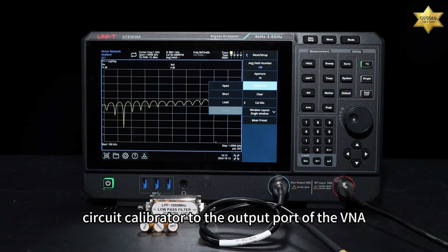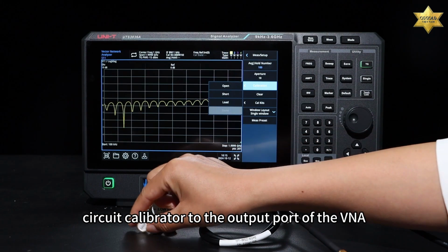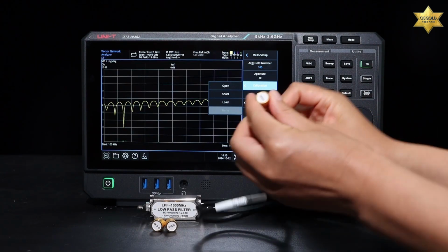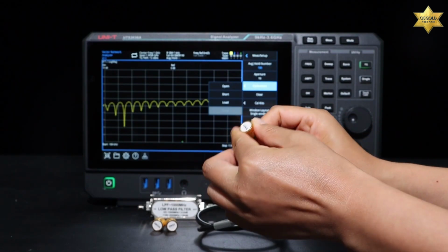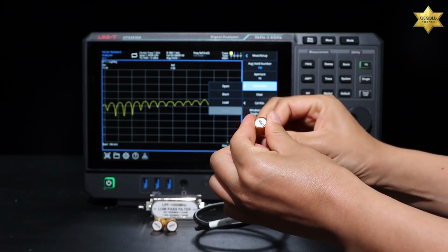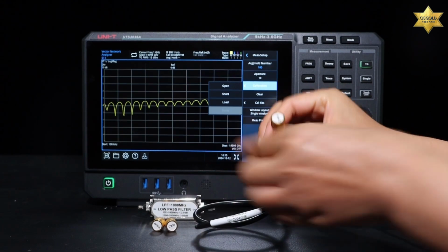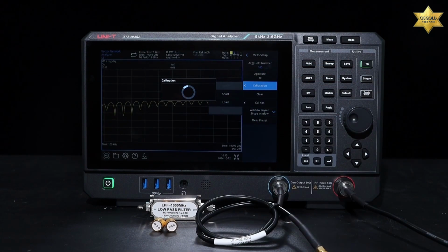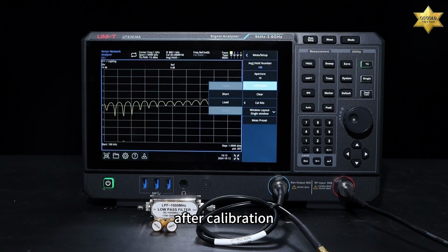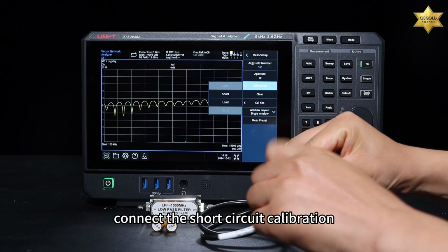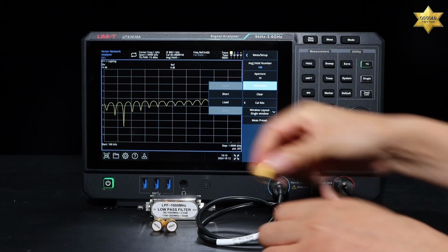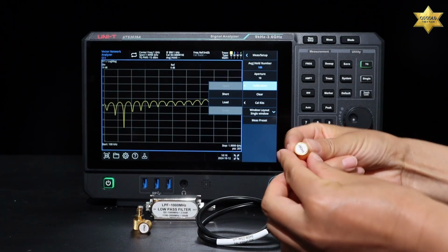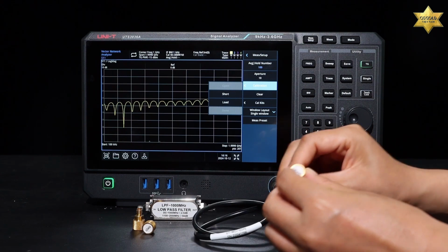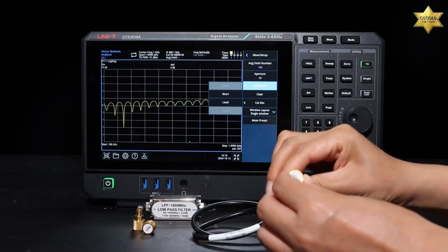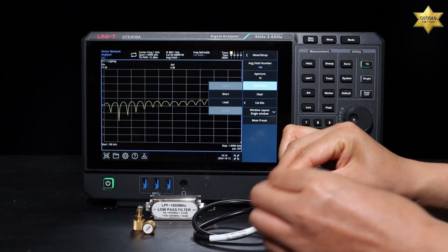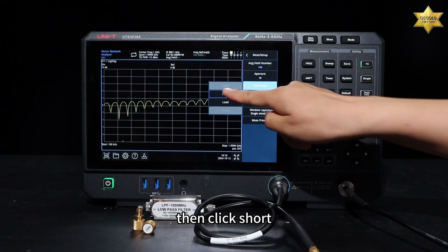Let's connect the open circuit calibrator to an output port of the VNA. Click Open. After calibration, connect the short circuit calibration kit to the output port of the VNA. Then click Short.